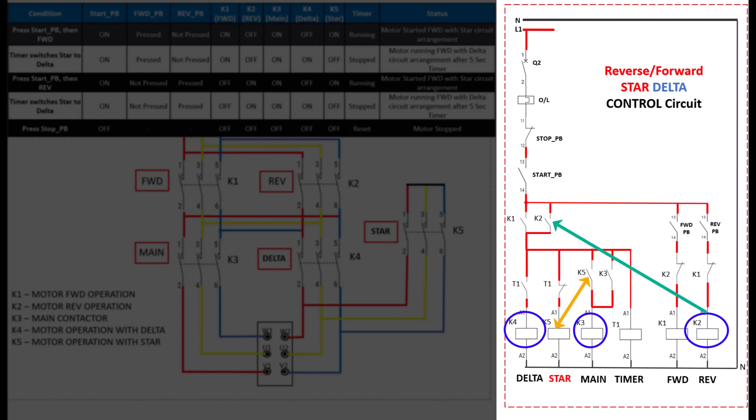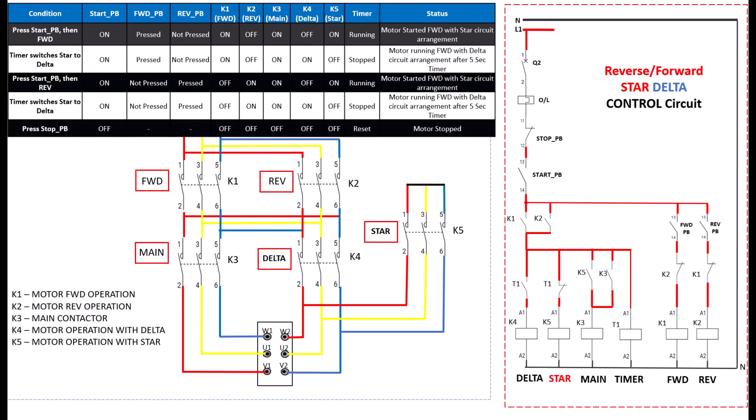You also see that K3 main contactor will not energize until K5 star contactor engages. This is also an interlock or condition. The purpose is to engage both the K3 main contactor and K5 star contactor together.